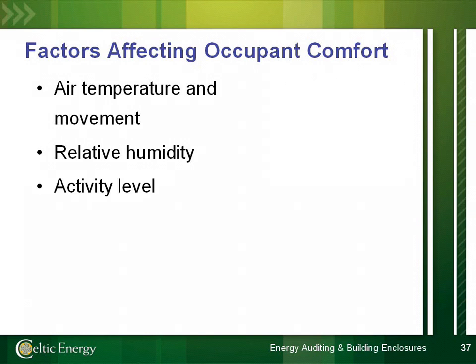Controlling relative humidity is also very important from a building preservation aspect, because unmanaged intrusion of moisture into or out of a building can cause significant damage that would have costly impacts on repair. The activity level that is occurring is also a big factor for occupant comfort. If it's an industrial site and there's physical work going on, those employees and occupants will have an additional heat source that will not be present in an office building with a sedentary work environment.